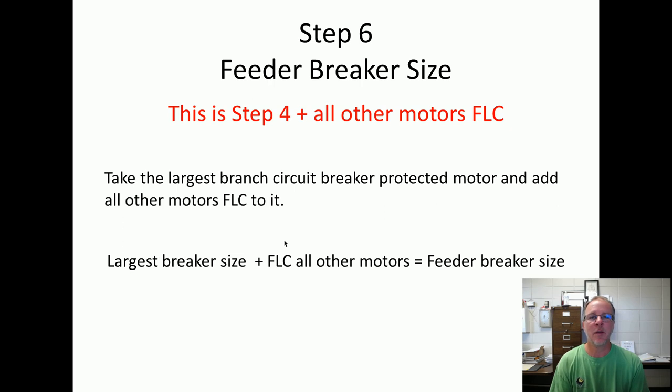All step 6 is step 4 plus all other motors' full load current. So if you can do the video for step 3 and 4, obviously you can do the video for 5 and 6, or the questions. So step 4, what it says is take the largest branch circuit breaker protected motor and add all other full load currents to it.